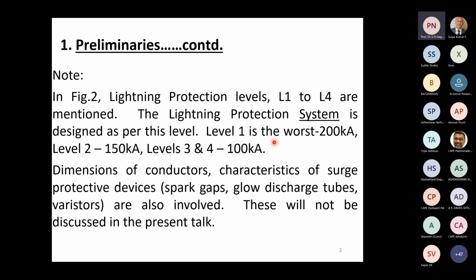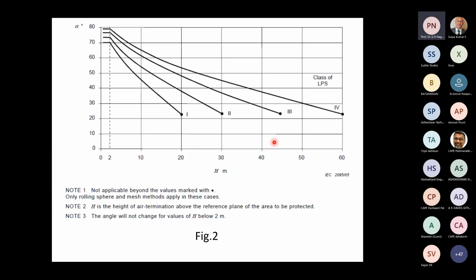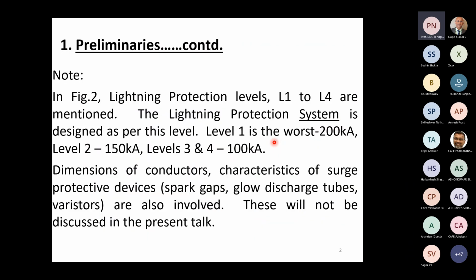Now, as I mentioned to you, lightning protection levels L1 to L4 are mentioned in the figure. Sorry, the table is missing here. Okay, it doesn't matter. The current levels corresponding to these systems are shown here. Now, dimensions of the conductors, characteristics of protective devices like spark gaps, glow discharge tubes, varistors are also involved. The specifications and technical requirements, and how they are met, we will not be discussing in the present talk because that itself can be a huge course, not merely 1 or 2 or 3 webinars. Characteristics of each of these devices can require more than 1 webinar for understanding it fully.